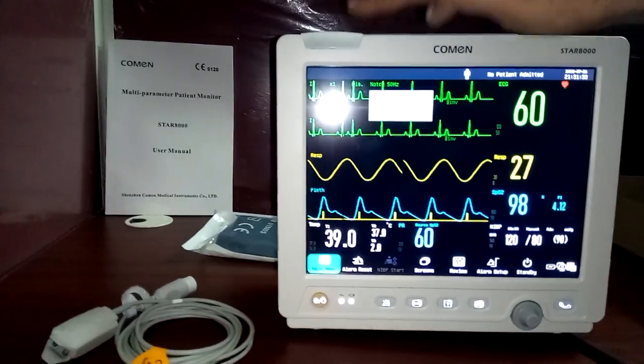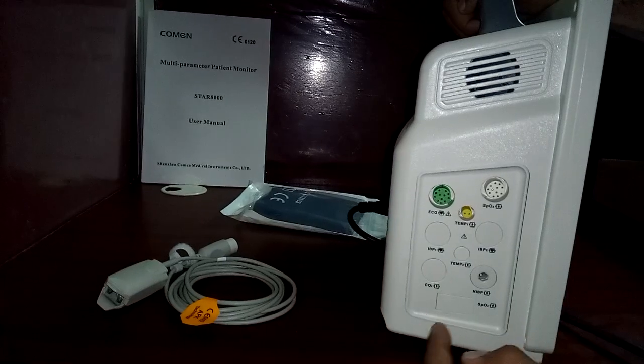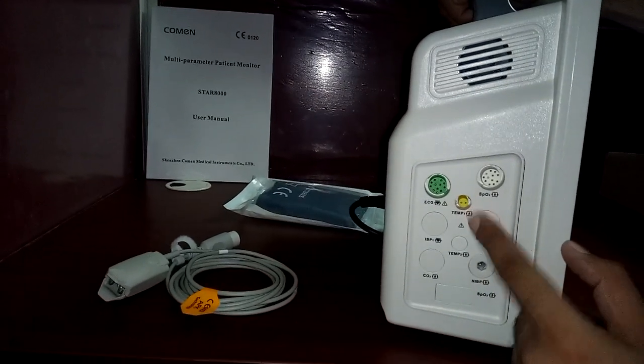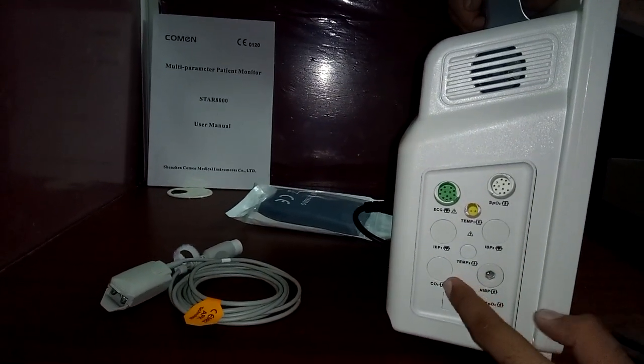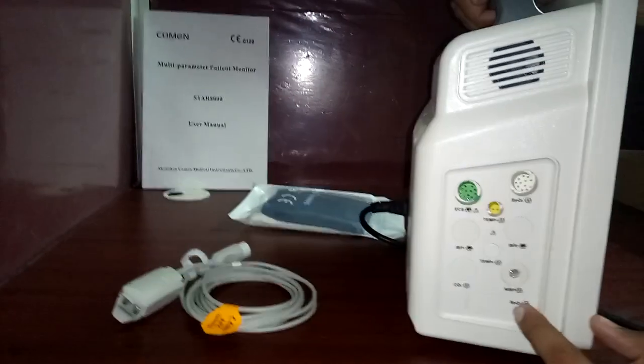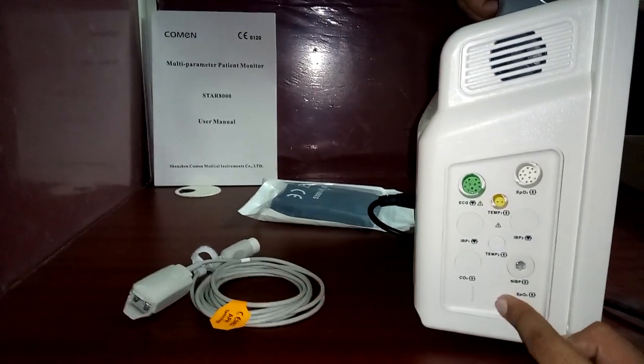The parameters available include ECG, SpO2, NIBP, and temperature as standard. Dual invasive pressure is optional, CO2 monitoring is an optional add-on, and Masimo SpO2 is also an optional item. You can also upgrade to a second temperature channel.